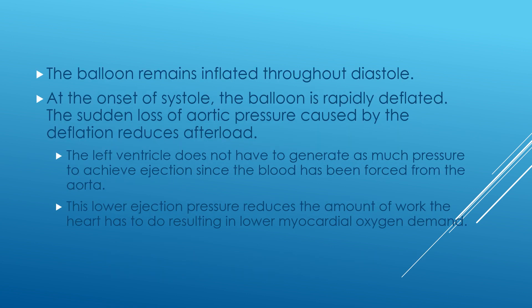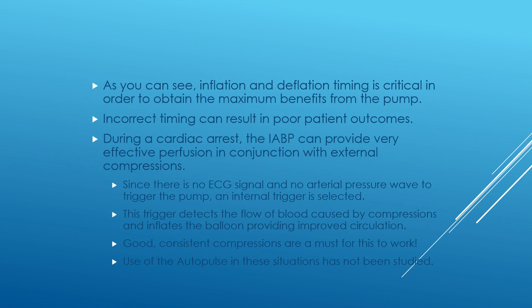The balloon remains inflated throughout diastole. At the onset of systole, the balloon is rapidly deflated. The sudden loss of aortic pressure caused by deflation reduces the afterload. The ventricle does not have to generate as much pressure to achieve ejection since blood has been forced from the aorta. The lower ejection pressure reduces the amount of work the heart has to do, resulting in a lower myocardial oxygen demand. As you can see, the inflation and deflation timing is critical in order to obtain the maximum benefits from the pump, and incorrect timing can result in poor patient outcomes.